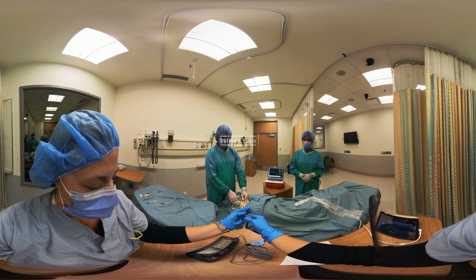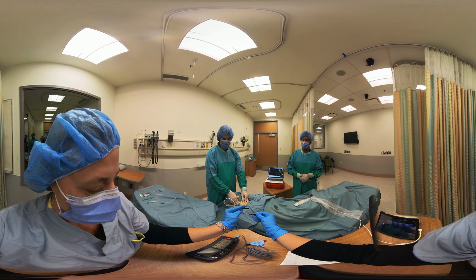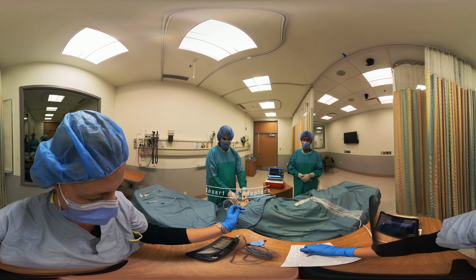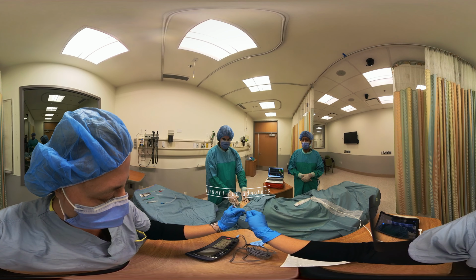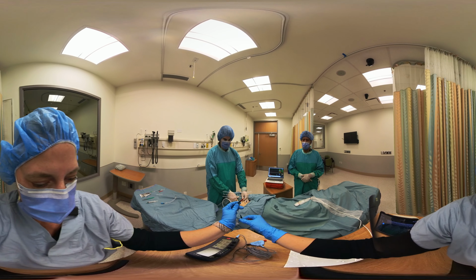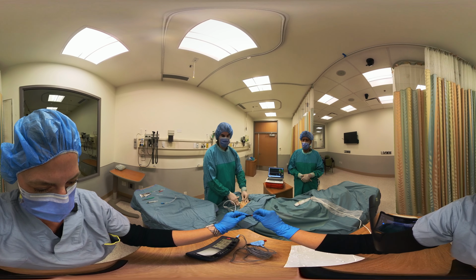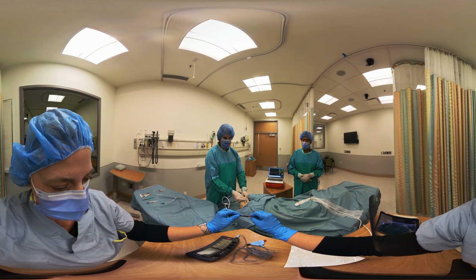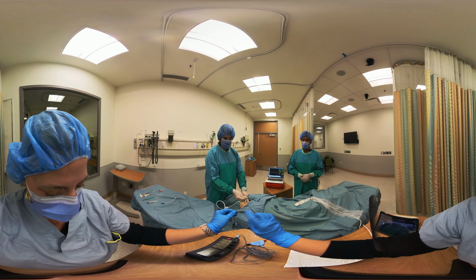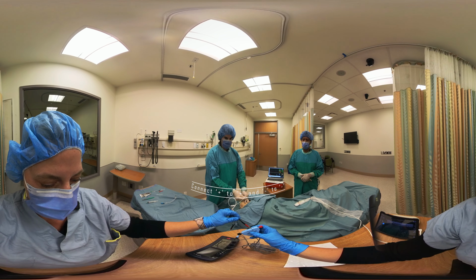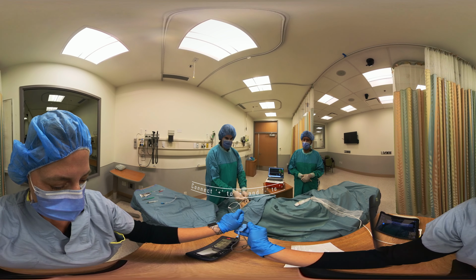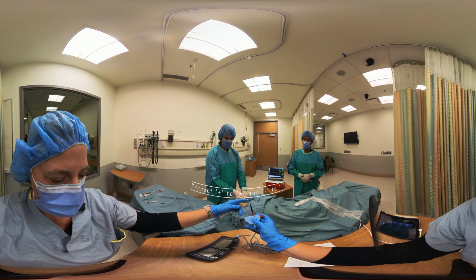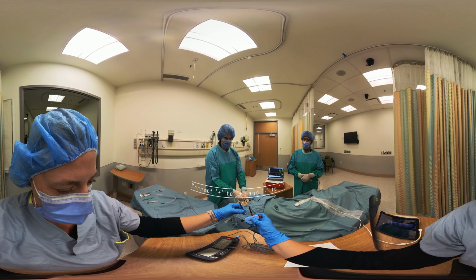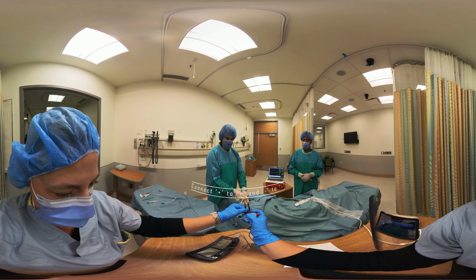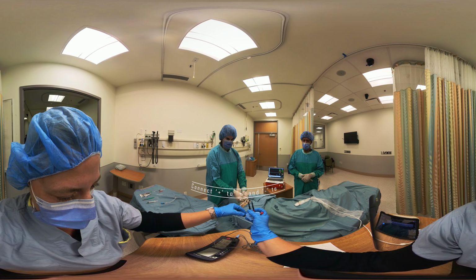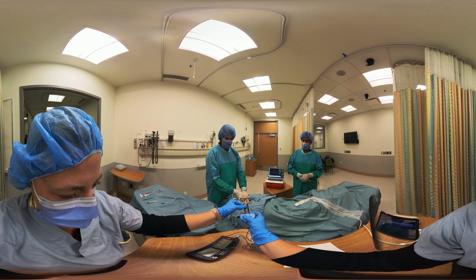Next, we're going to get the rest of this catheter ready to go. We're going to take the two black ends of the catheter, and we need to insert the red colored adapters as such. Once we insert the two red colored adapters, you will then connect the positive to the plus side of the wire that comes out of the pacing box. Once that is inserted, you turn the red colored knob, which screws it in and makes sure that it cannot be removed. Same thing with the negative post: you will insert it into the other end of the wire. Once it is tightened and cannot be removed, we will then prepare for pacing.